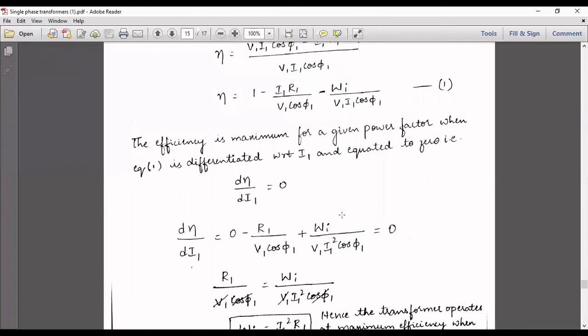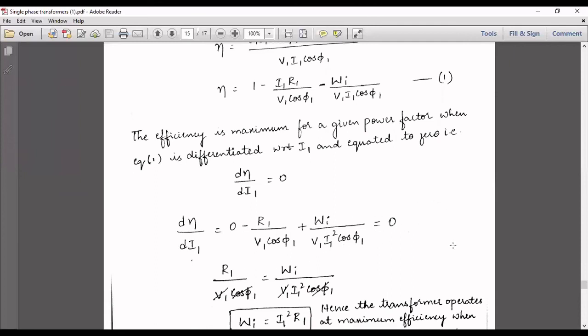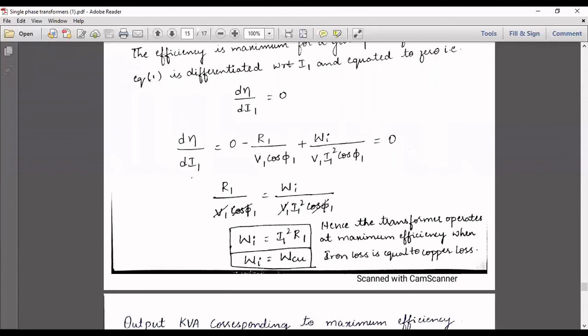So d eta divided by dI1 will be 0 minus R1 by V1 cos phi 1 plus WI by V1 I1 square cos phi 1, which is equated to 0. If this equation is simplified, I get WI equal to I1 square R1. That is, iron loss is equal to copper loss. Hence, the transformer operates at maximum efficiency when iron loss is equal to copper loss.